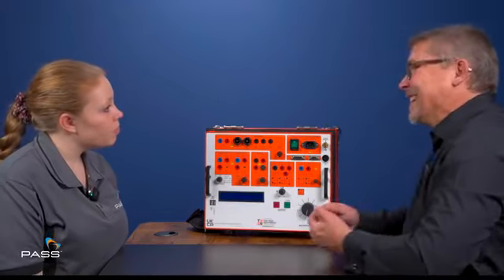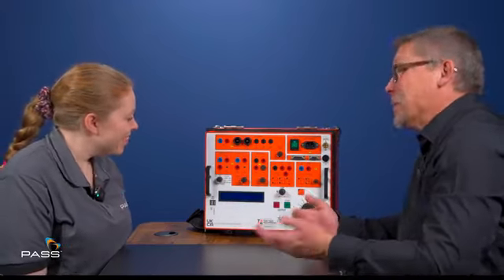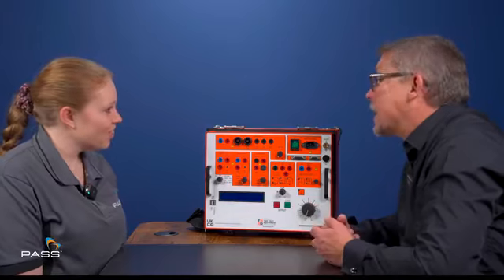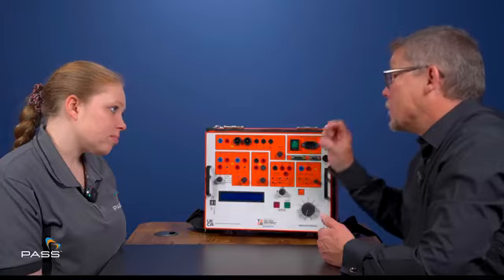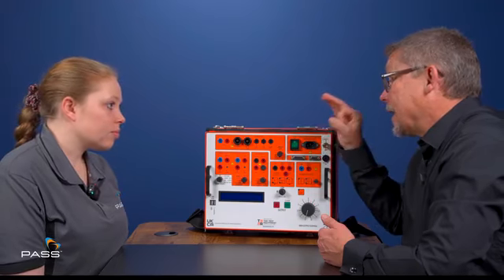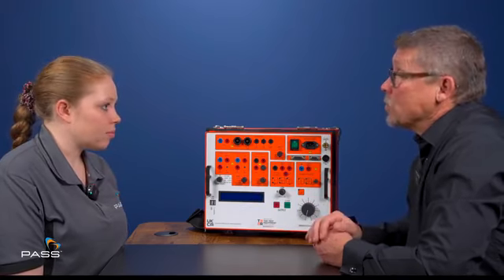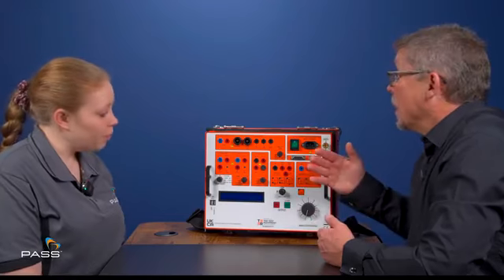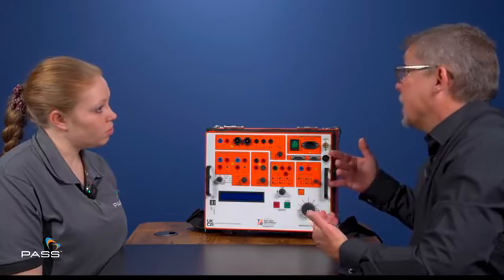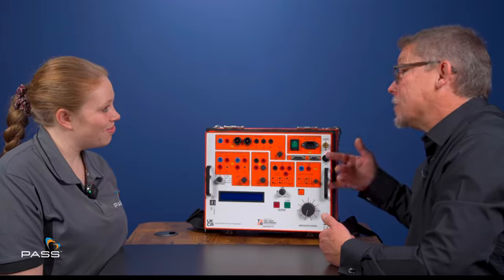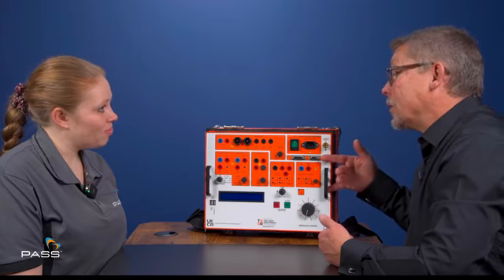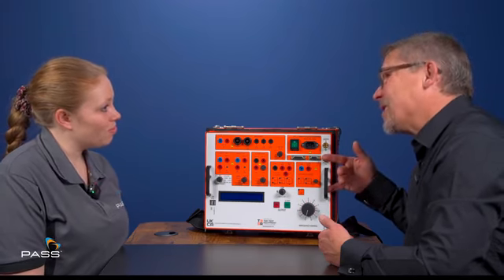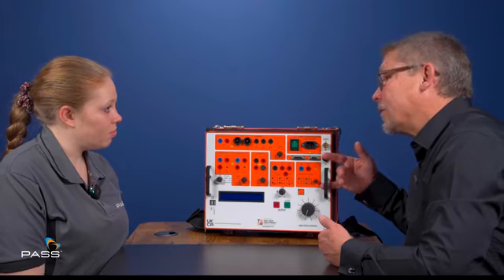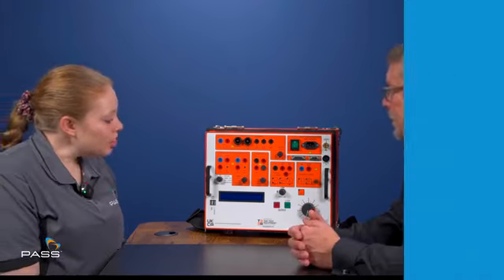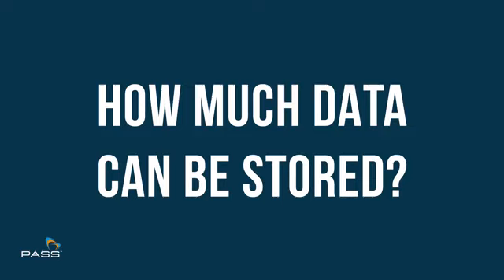Set clock, I think that's pretty self-explanatory. We set the time, we set the date, and once it's set, it's stored. Now, the way that it stores the data in the machine is we've got a little penny battery in there, and that actually holds all that memory within the unit itself. Because again, you could be forgiven for looking at this unit. It looks kind of old-fashioned. It's almost like what we've done is we've got a unit that looks like a Model T, but actually, it's a bit like the latest Ford Focus. So how much data can it store? How big's your memory stick?